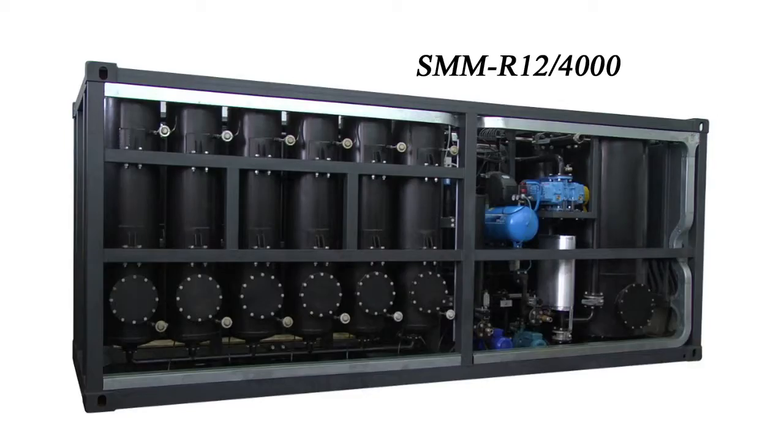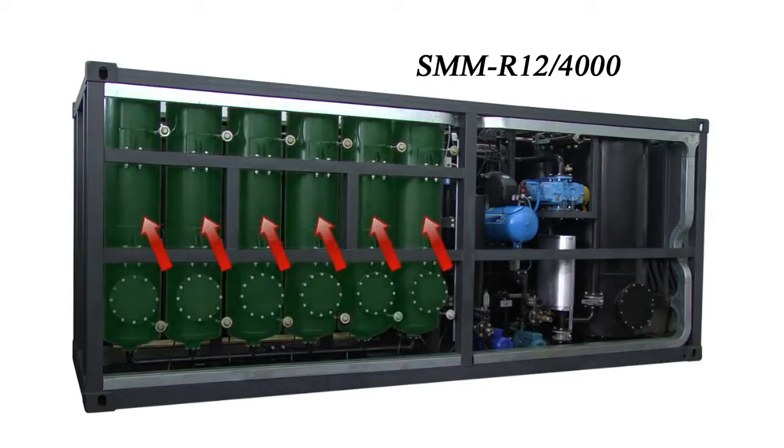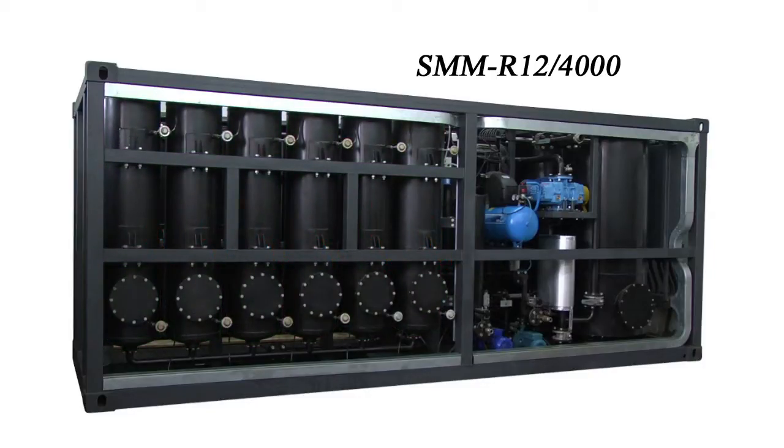The sorbent in the column is the primary agent in the system. During operation, the oil percolates through a stationary sorbent layer and regenerates and filtrates on contact. After regeneration, the oil goes to a filter for final purification from solid impurities and filtration of oil. After sorbent saturation by the products of oil decomposition, the system switches to sorbent reactivation mode.